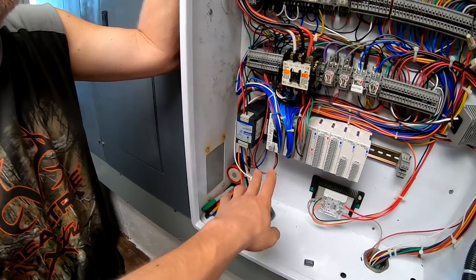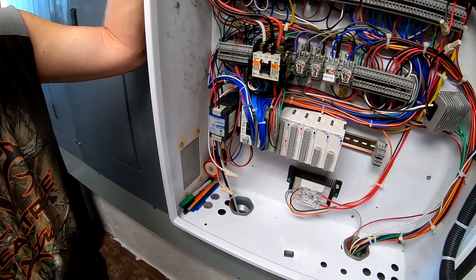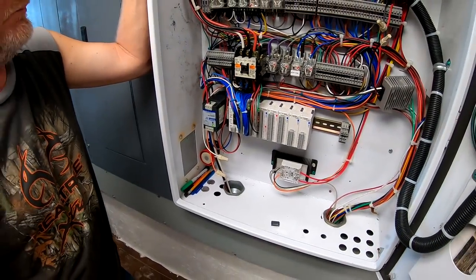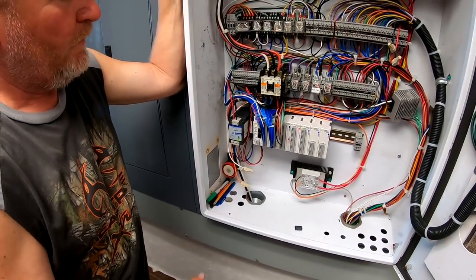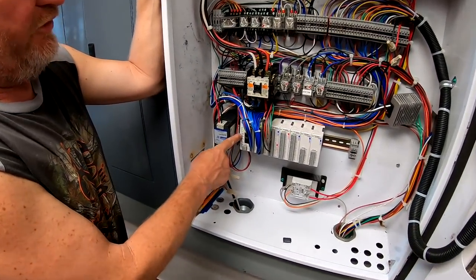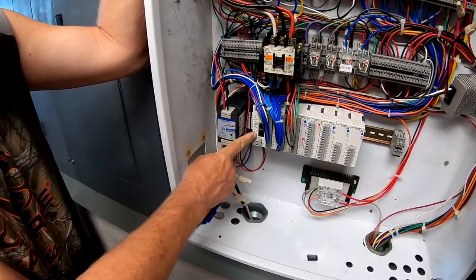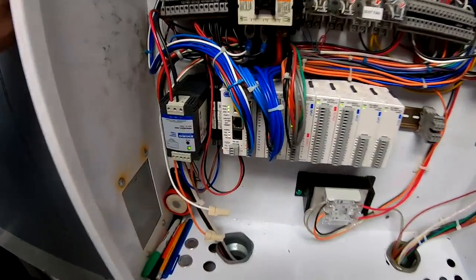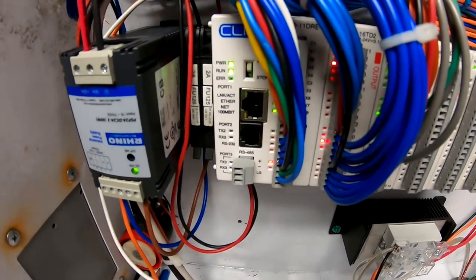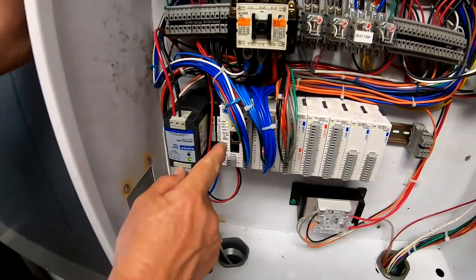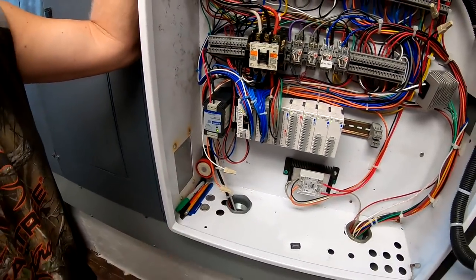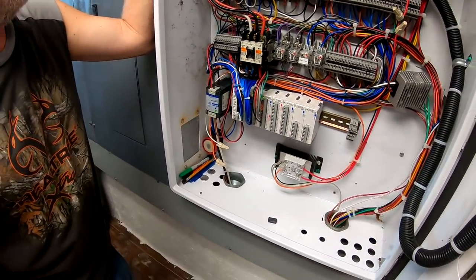So this box right here converts from your 46 to 60 volts coming from the batteries to a nice solid 24 volts that powers the brain box and the whole control panel. So then is this one here the brain box? Yeah, that's the brain box. You program it right there through that Ethernet port that connects right up to the laptop.